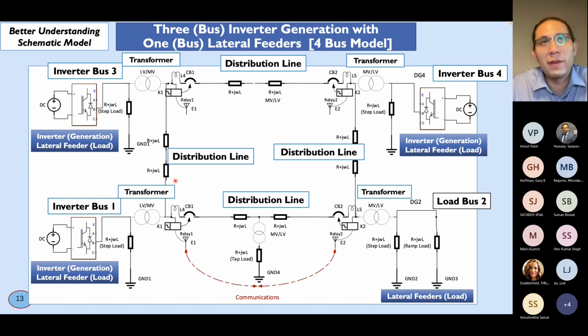So usually our voltage level in the low voltage will be 120 to 140, and this can range up to 220, depending on the country, either US or Europe. And in the distribution line, since this is a distribution grid, our voltage goes up to 4.1 kilovolts. Based on the literature, this is a medium voltage, but still in the low voltage setting because it is not passing 10,000. So it depends on the country. That's basically the main explanation here.